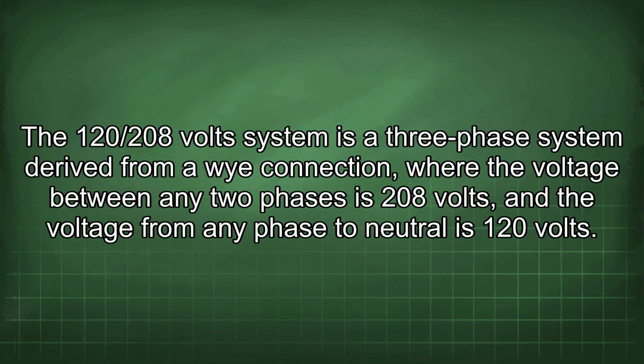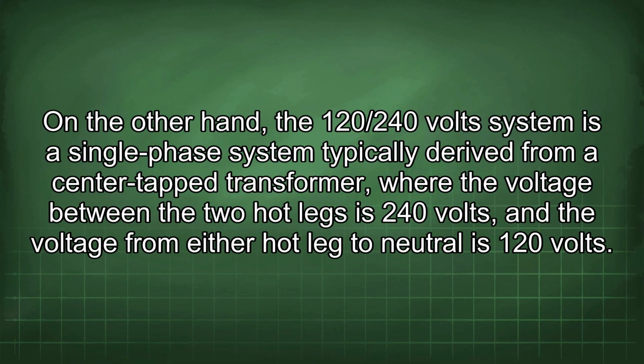The 120/208 volt system is a three-phase system derived from a Y connection, with the voltage between any two phases is 208 volts, and the voltage from any phase to neutral is 120 volts. On the other hand, the 120/240 volt system is a single-phase system typically derived from a center-tap transformer, where the voltage between the two hot legs is 240 volts, and the voltage from either hot leg to neutral is 120 volts.